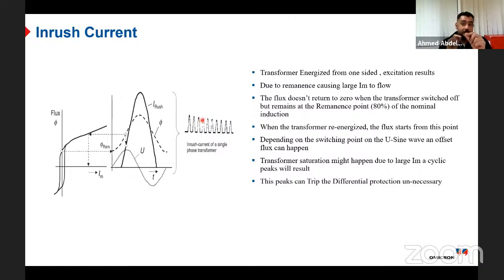We can say yes, the percentage of the second harmonic content in the inrush current while I'm energizing a transformer is 20%, so I can give a tolerance of 25%. So if the second harmonic content is less than 25%, it means this is not an inrush, this is a clear fault, a differential fault, and then I need to trip the circuit breaker. There are so many things I need to take into consideration.